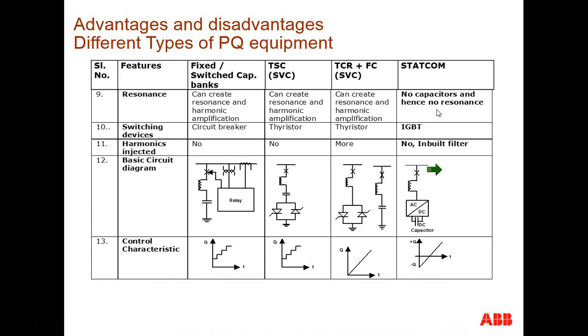In terms of response, with the capacitor the response is very slow because it takes time to discharge the capacitor before you energize or reconnect the capacitor. In case of switching devices, in SVC mostly thyristors are used, and in the STATCOM it is also IGBT or IGCT used. Harmonics are generated, so an inbuilt filter is adopted.